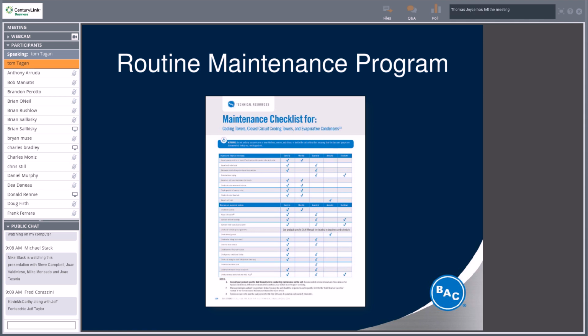The other item to be aware of is any excessive noise or vibration, because you're going to want to look for any imbalance on the fans. Maybe you got a loose belt, maybe there's an issue with a gear, or maybe you're headed towards bearing failure. Another thing it lists here is inspect the cold and hot water basins. Again, checking for leaks, make sure that the water levels are satisfactory, make sure you're getting even distribution over the fill. We're going to touch on these points in a little bit more detail later on, but I just wanted to kind of call them out for you.